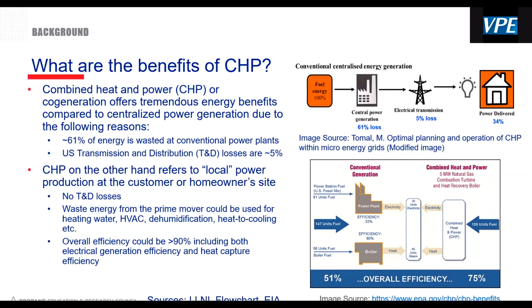On top of that, the waste heat from a CHP unit can be tapped for hot water and space heating needs, which is the antithesis of a power plant, where rejected heat is sent out into the environment through cooling towers. Hence CHP has a net efficiency much higher than a central power plant. Typical CHP units can exceed 90% efficiency, or even higher, on a fuel lower heating value basis—about 30-35% from electricity generation, and 50 to 60% from heat capture.